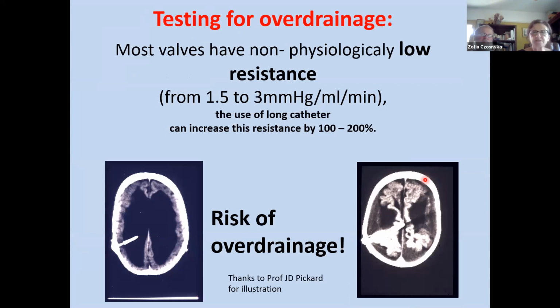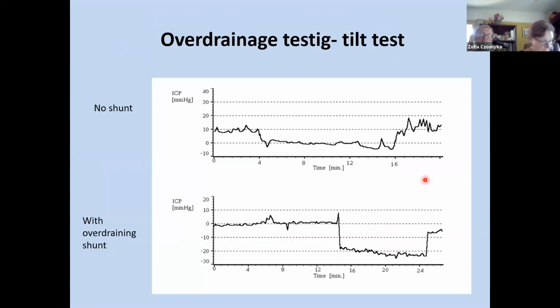Overdrainage. The excess is also undesirable. The cause of excessive drainage can be various. The low hydrodynamic resistance of most valves may enhance this risk significantly. Most common is postural overdrainage. A simple tilt test can help to reveal whether the system is working optimally.